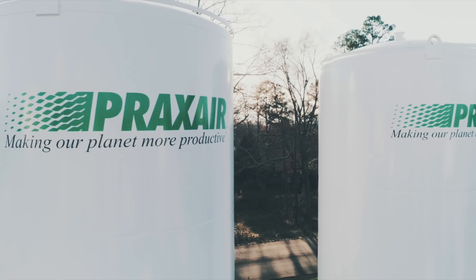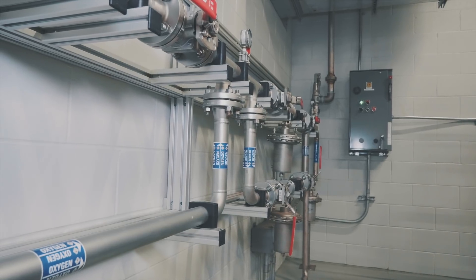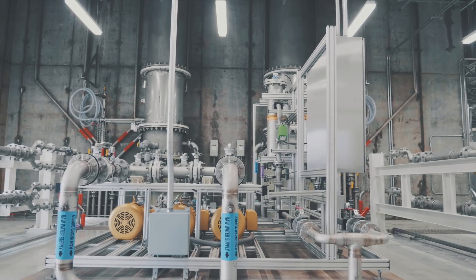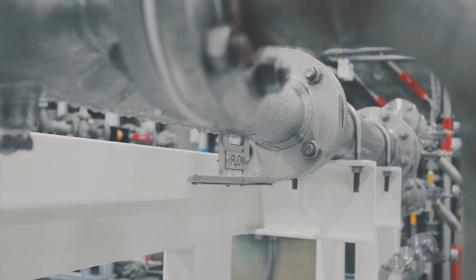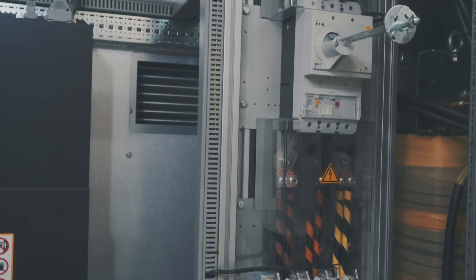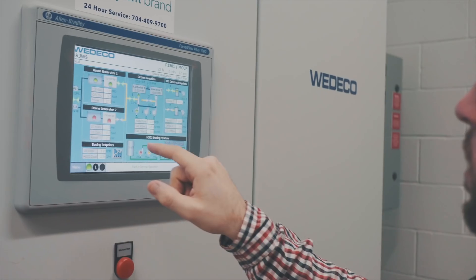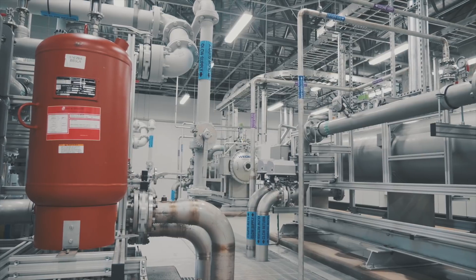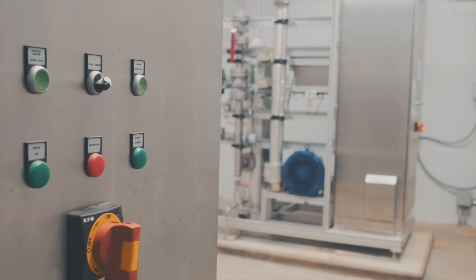Ancillary components consist of a liquid oxygen feed system, gaseous oxygen manifold, a nitrogen boost system, dissolution pump skid and pre-dispersion skid to ensure optimal mass transfer efficiency, power supply units and control system which provide electricity and logic behind the operation, open and closed cooling water systems to minimize heat build-up, and destruct units to eliminate ozone off-gas in the atmosphere.